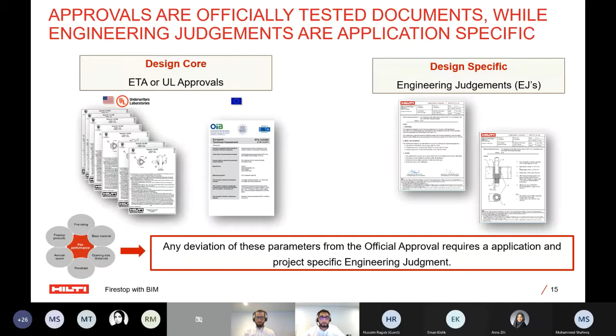So this is a fire stopping system that is based on the American standard and has been tested by the UL third-party laboratory. So it has a unique number, which you see here, CAJ1421. It has a brief description of what this system represents. So this is for a metal pipe passing through a sleeve in a concrete floor or a wall. And it provides you either a 2 or 3 hour fire rating, depending on some parameters that we will see later on.